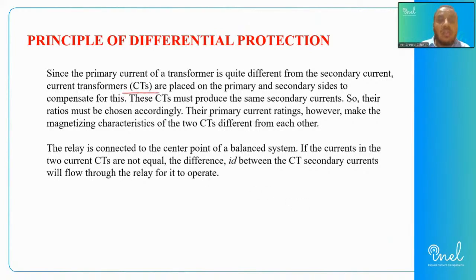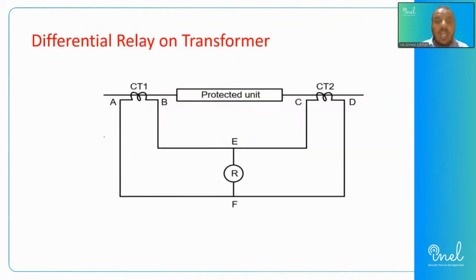We will add a bunch of current transformers. Those current transformers should sense, so measure, the current, and from those measurements we can calculate using the relay. So the relay will accept all signals from the current transformers. Such a relay will confirm the processing: whether the summation of I in minus summation of I out equals 0, so we are normal, or there is a difference, so we should act. And that is exactly how a differential relay would be implemented.